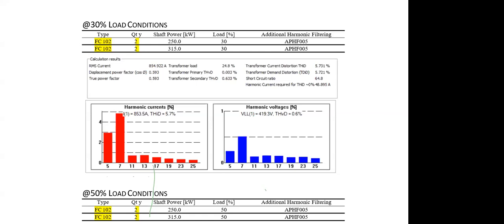This is also equally important: in which load condition you are doing this analysis. Any system always operates perfectly, or very close to its design condition, when it operates at full load. When it comes to partial load, all the problems start. Mostly it applies to all equipment. For example, if you operate a motor at its full load condition, 100%, it gives you a power factor of almost 0.9 to 0.92. Fantastic. As you come to three-quarter load, it goes below 0.8. If you do half, it is 0.7 and so on. So this is how this looks.